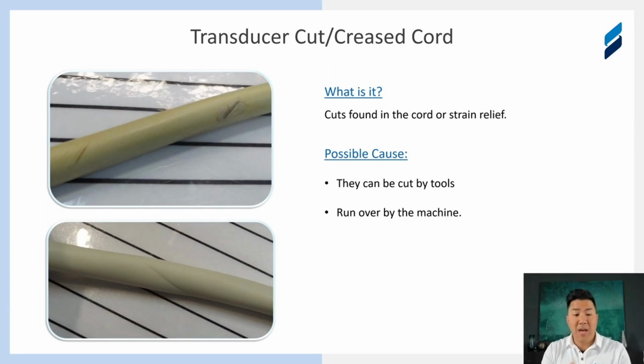The same thing can happen if it's just run over by a machine or accidentally gets into a door jam and gets pinched off and crushes all the wires together. So now you have all these wires that are crushed together and creased. When you see a crease, that will cause chafing and unnecessary shorting between all the microcoaxial wires on the inside. So this is just something to really look at, because that's a very possible cause where you have image quality issues.